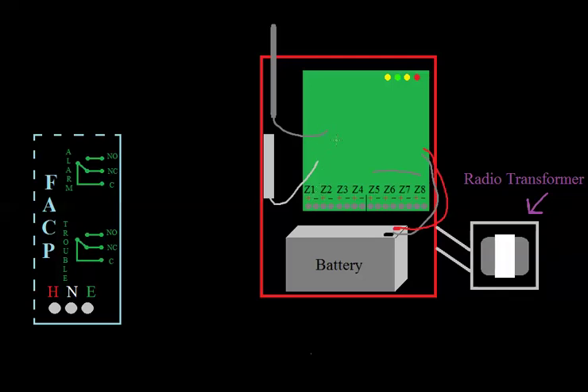It's going to send some code. It says this radio account number, let's say this is account number 1,000, just had an open circuit on zone 1 or a short circuit on zone 1. And it's going to be a long data code that has the account number and the zone and what type of, whether it was an open or a short, that's its own data code, or whether it's restored, it sees its resistor. But this side of it works just like a fire alarm panel.